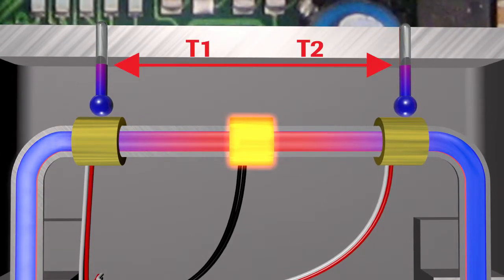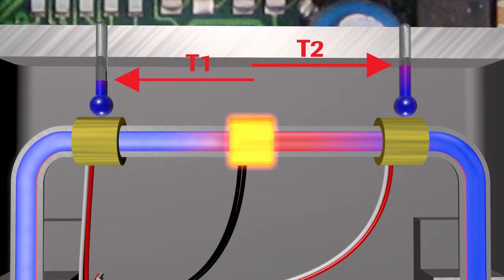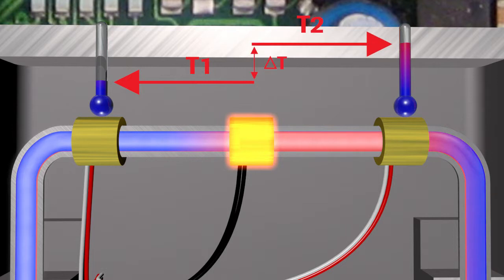This cold gas cools the first temperature recorder. The second sees the gas that has been heated by the heater. According to the law of energy retention, the temperature difference is a direct measure for the mass flow.